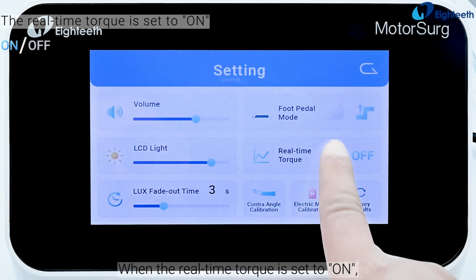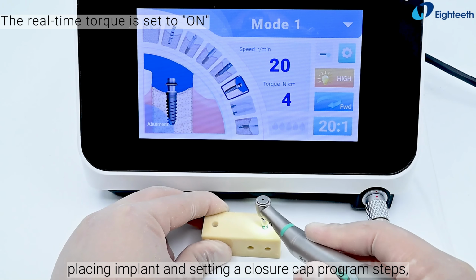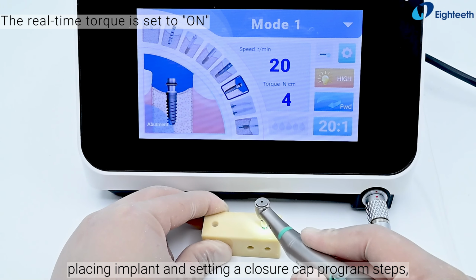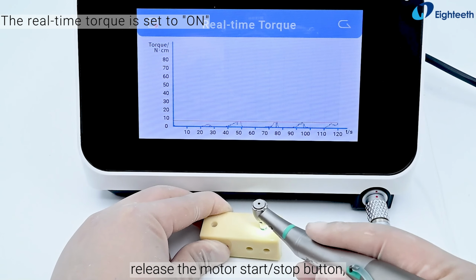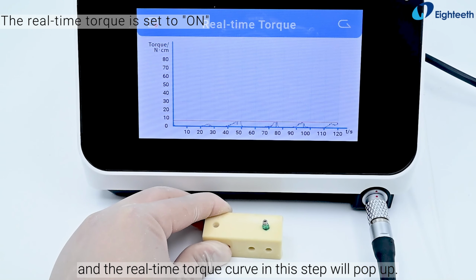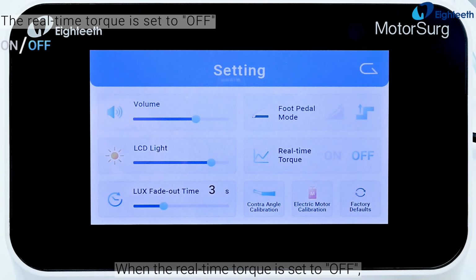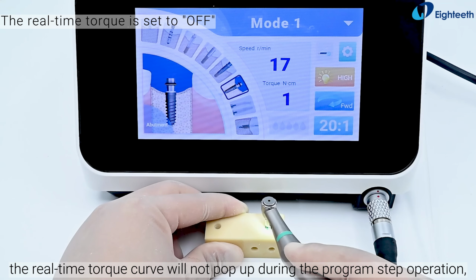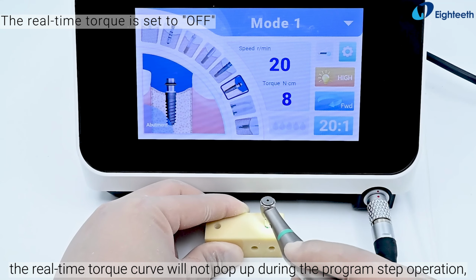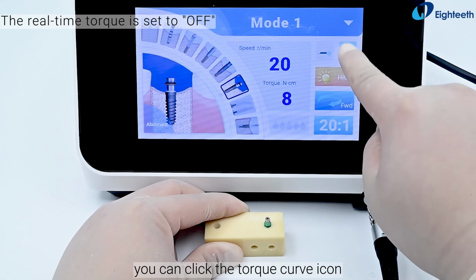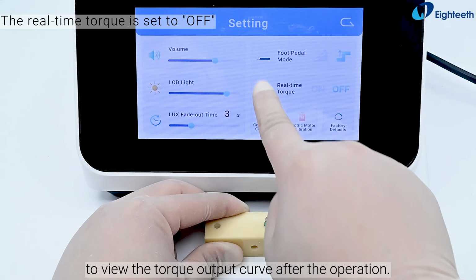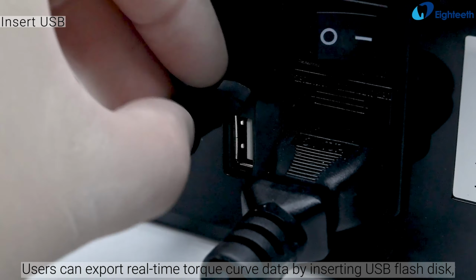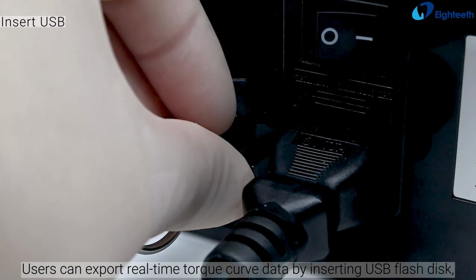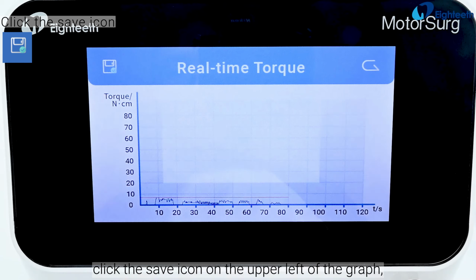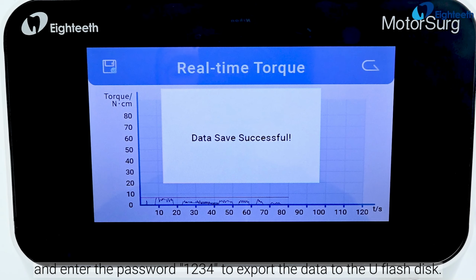When the real-time torque is set to on, during the tapping, placing implant and setting a closure cap program steps, release the motor start/stop button, and the real-time torque curve in this step will pop up. When the real-time torque is set to off, the real-time torque curve will not pop up during the program step operation. You can click the torque curve icon to view the torque output curve after the operation. Users can export real-time torque curve data by inserting USB flash disk. Click the Save icon on the upper left of the graph, and enter the password 1234 to export the data to the flash disk.